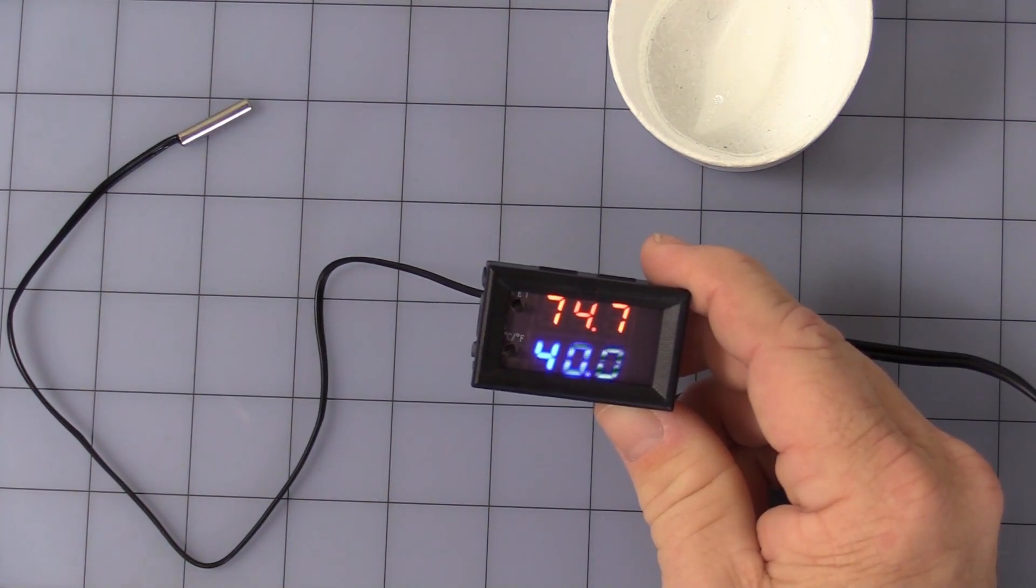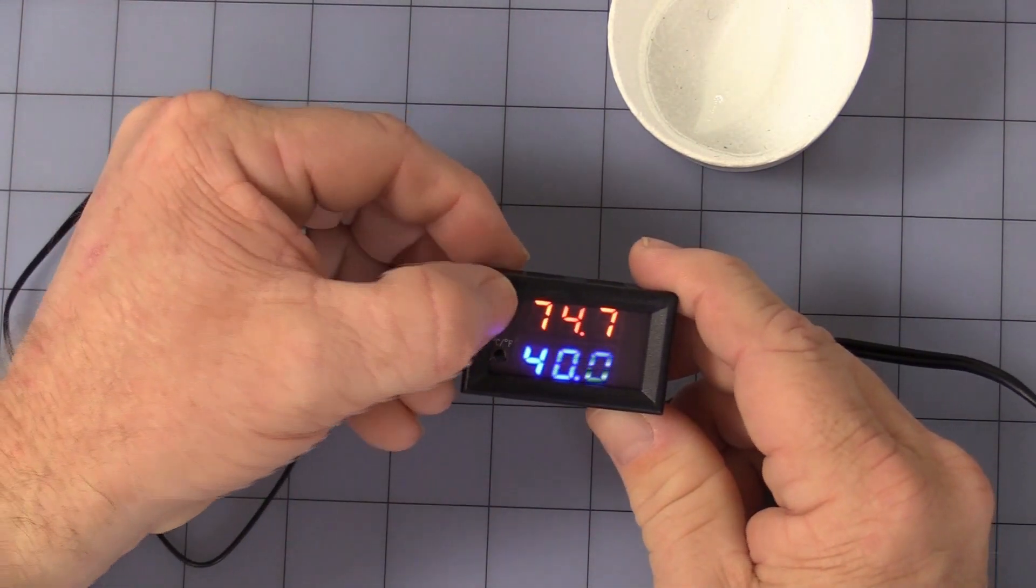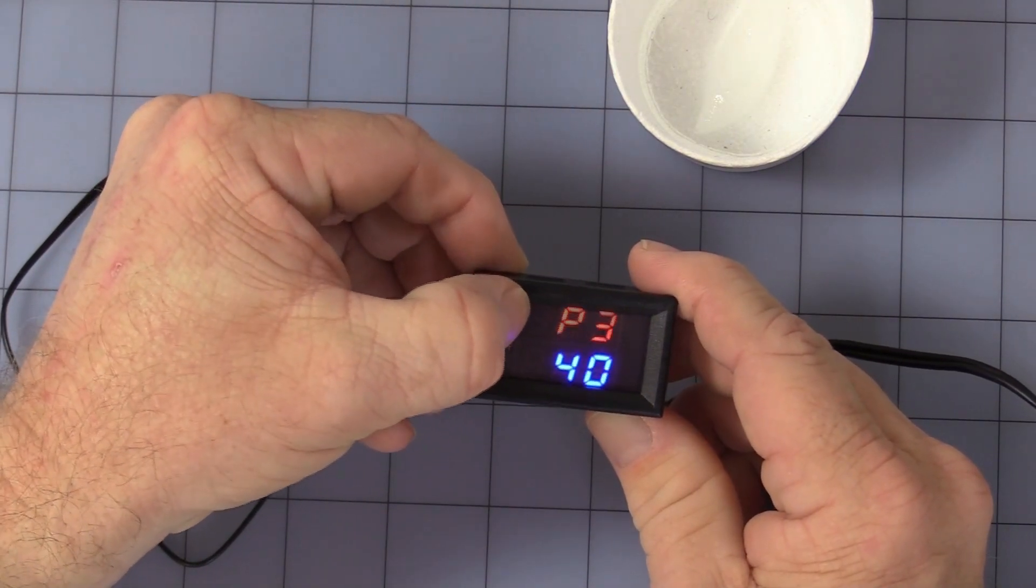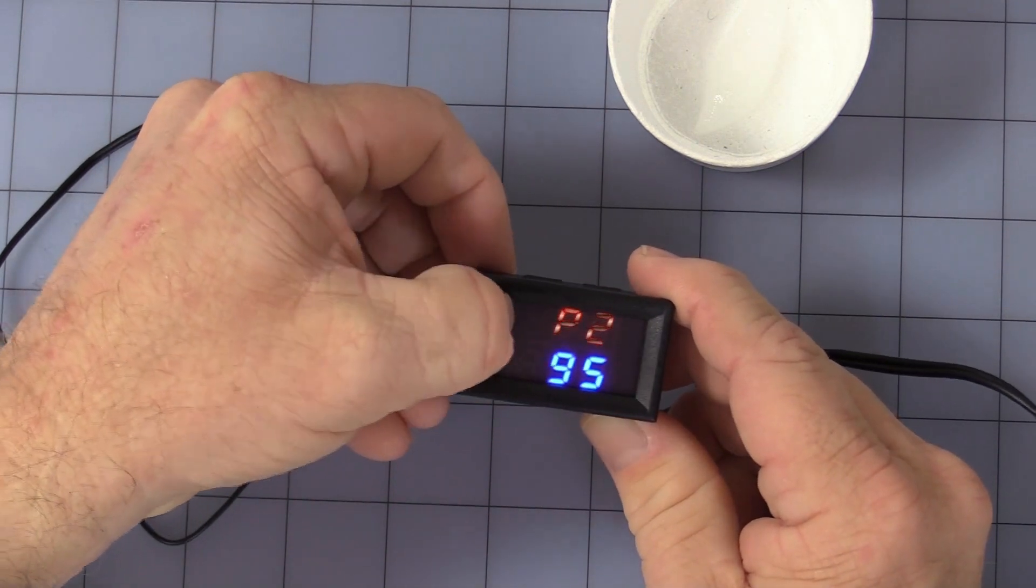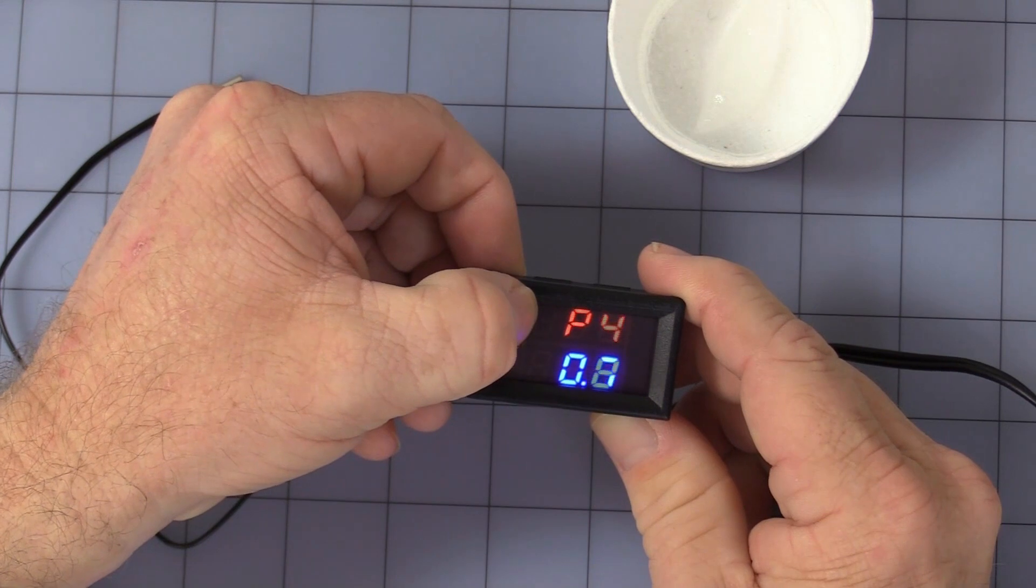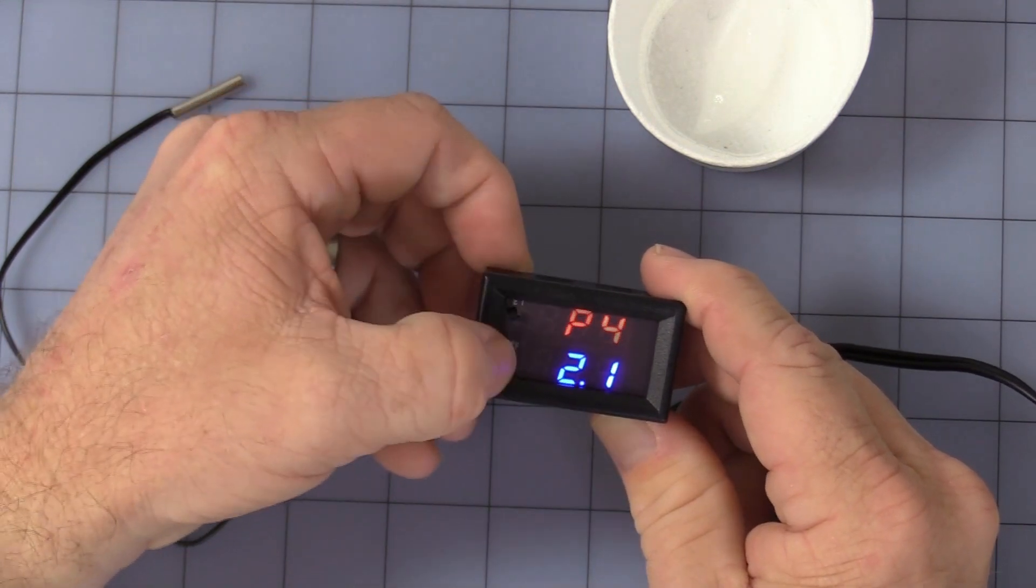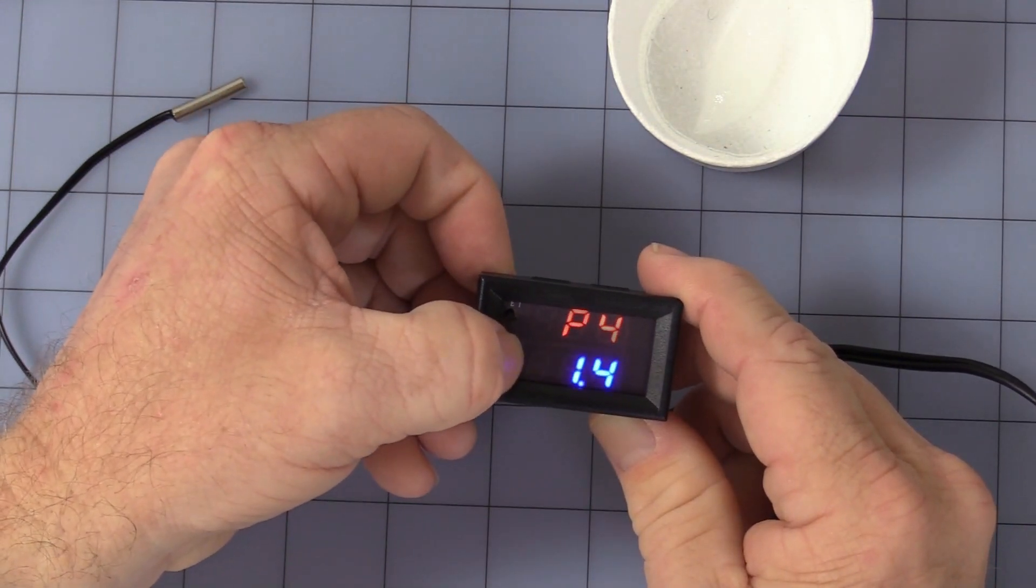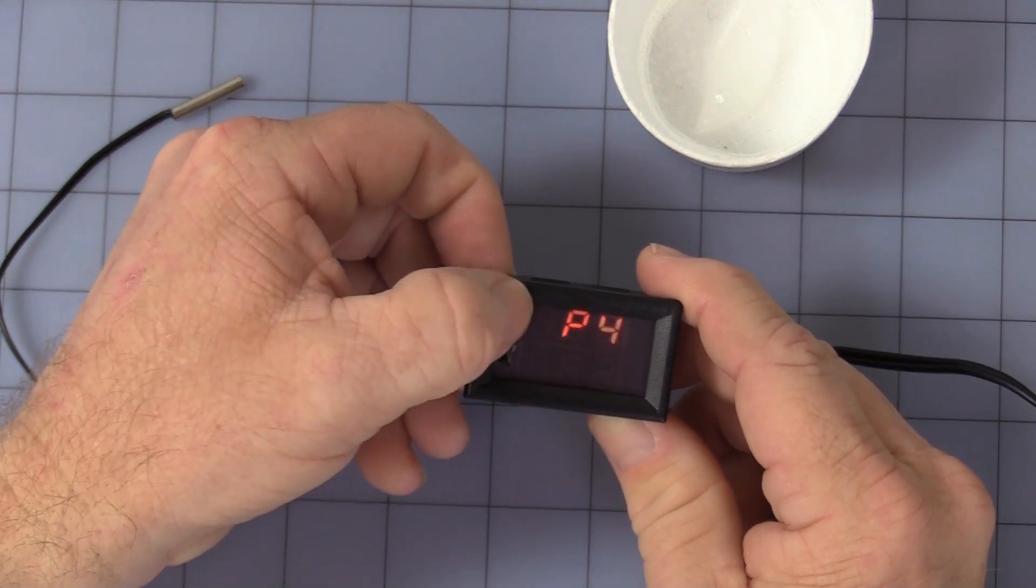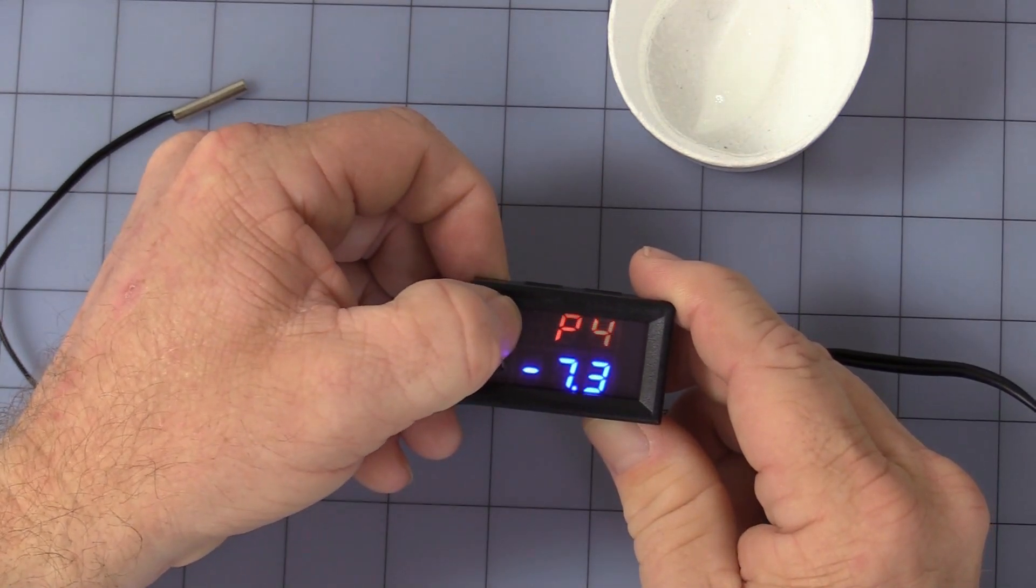Once it stops flashing, it goes back to program. Now, we get into P4, which is a temperature correction. Let's say you run a long-distance cable and you need to correct, compensate for any temperature difference. You can adjust it from plus or minus 15 degrees, but it's factory set at zero.